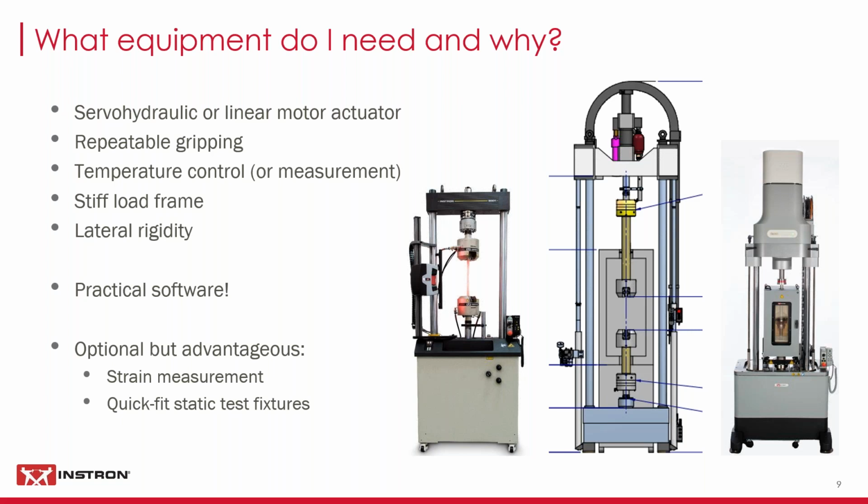The other thing that we see is very, very popular in machine purchases is the ability to what we call piggyback, to quick fit static test fixtures on top of those fatigue grips, so that you can pick up a little bit of capacity and maybe do some flexural static tests as well, without completely demounting your fatigue load string. It just gives you a little bit of extra capability for the machine.